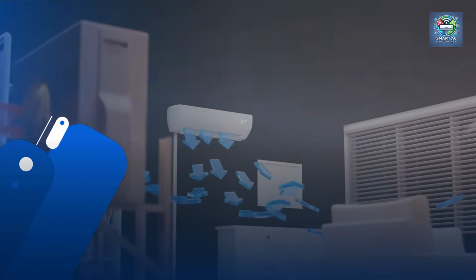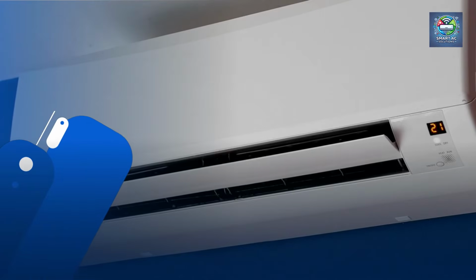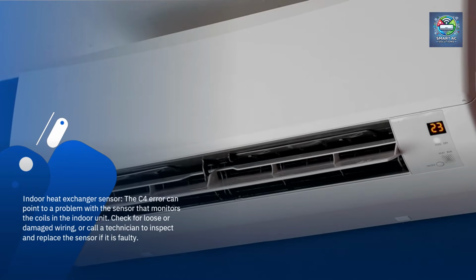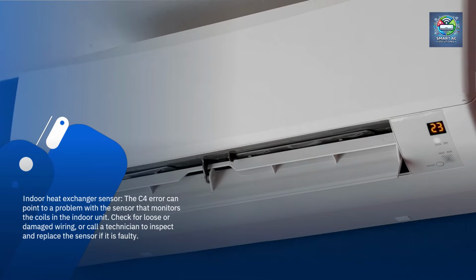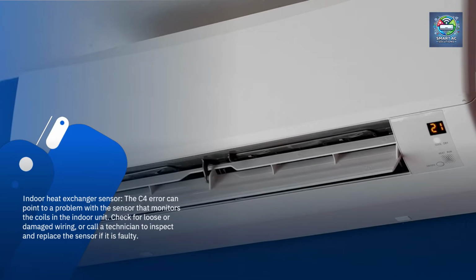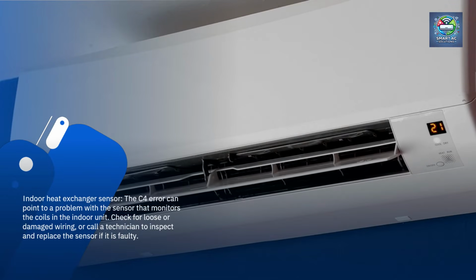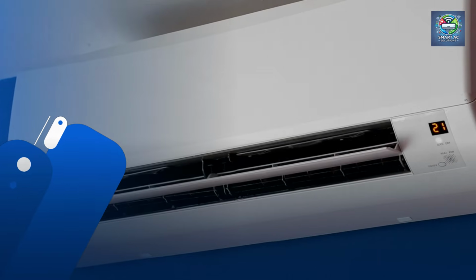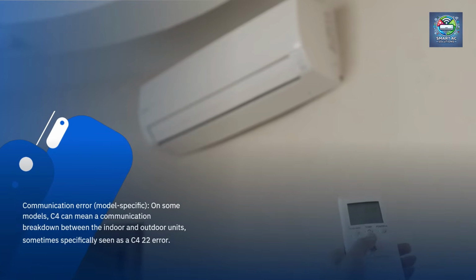Here are some potential causes and solutions. Indoor heat exchanger sensor. The C4 error can point to a problem with the sensor that monitors the coils in the indoor unit. Check for loose or damaged wiring, or call a technician to inspect and replace the sensor if it is faulty. Communication error, model specific.